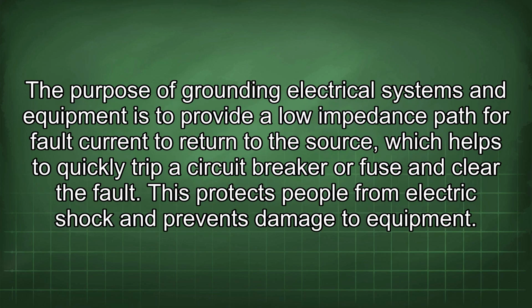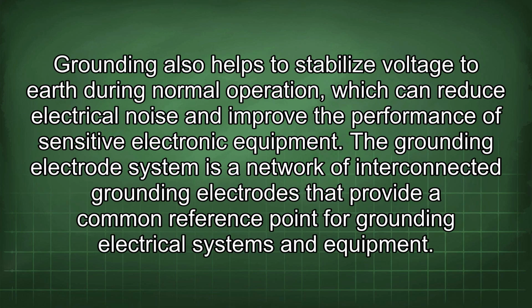The purpose of grounding electrical systems and equipment is to provide a low impedance path for fault current to return to the source, which helps to quickly trip a circuit breaker or fuse and clear the fault. This protects people from electric shock and prevents damage to equipment. Grounding also helps to stabilize voltage during normal operation, which can reduce electrical noise and improve the performance of sensitive electronic equipment. The grounding electrode system is a network of interconnected grounding electrodes that provide a common reference point for grounding electrical systems and equipment.